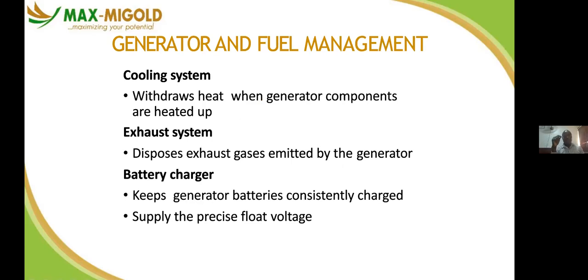The cooling system of a generator withdraws heat when generator components are heated up, like the exhaust. As the generator is heated up, the smoke is expelled through the exhaust. Then we have the battery charger. This helps to keep up the performance of your battery. It helps to charge it as the generator is draining it. The battery charger, that is the alternator charger, is charging your battery constantly so that the battery does not run out.